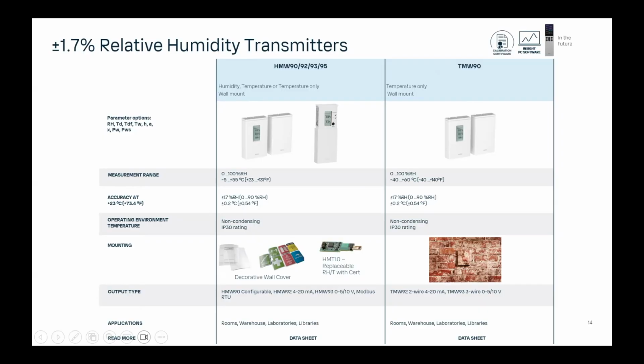It's shown right here as the HMT 10. This is just the module that houses the humidity and temperature chip. That can be pulled out and put right back in, and then pulled back into spec to get back to that plus or minus 1% humidity rating. One thing that's unique about these is this decorative cover you'll see. A lot of these are used in museums or spaces where you don't necessarily want to see the transmitter itself. Museums tend to think these don't fit in with their artwork or anything. We like the look of them, but if you want to hide them, you can insert either wallpaper or you could paint this. But you'll see on the right here, if you look closely, you can see that square and it's reading behind that, and it's actually ventilated, so it gets good airflow and can still get a good measurement, even though it might not be visible to everyone around.